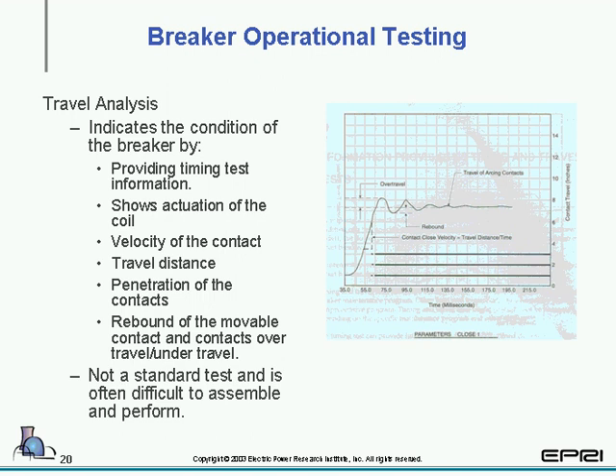Travel analyzers are typically not used because they tend to be cumbersome. The information you get can be interpreted in more than one way, and they are not easy to set up. You may require some form of a jig to actually get it to work on particular breakers. This requires special equipment. Again, if you don't do overhauls in house, you're likely not to have this equipment. It requires special jigs and so forth.